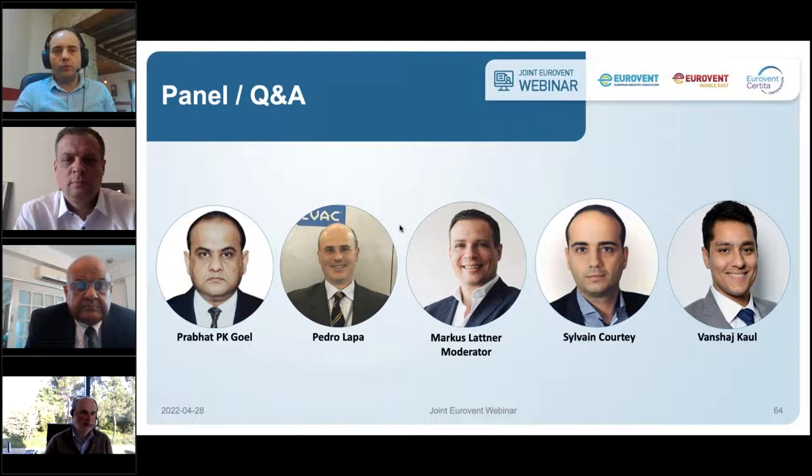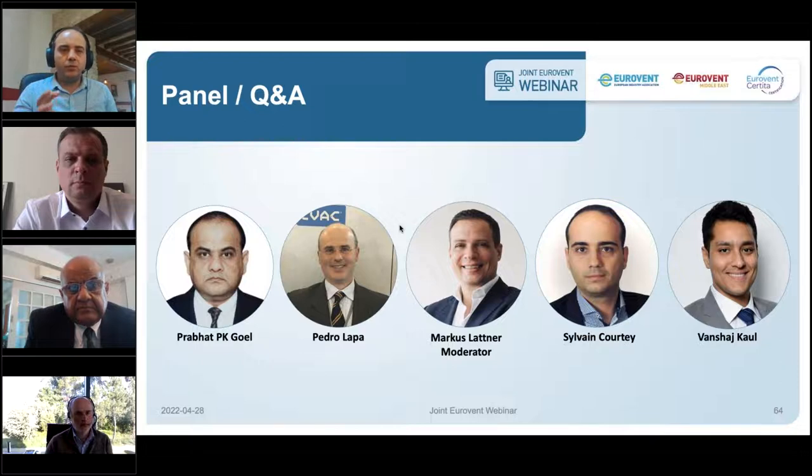But of course, we also rely on testing methods that are referred to in European standards. So basically EN 13053 for air handling units and EN 1886 for the casing. But for AHU energy efficiency classification, it's a specific document made by Eurovent and related to the certification program. Thank you.